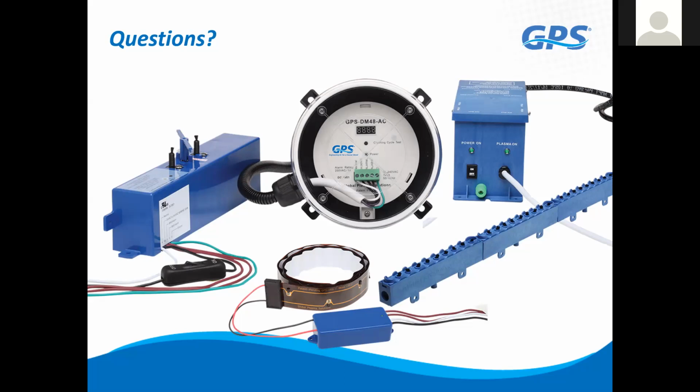Okay. What is the voltage at the emitter? Probably about, I measured it yesterday. I was doing a hands-on presentation, and I was measuring the voltage. At the auto cleaning, I was measuring about 5,500 volts DC. You got DC positive on one side, DC negative on the other. And on the iMod bar, I think I was reading about 6,500 or something. We want to read between 4,000 and 7,000.